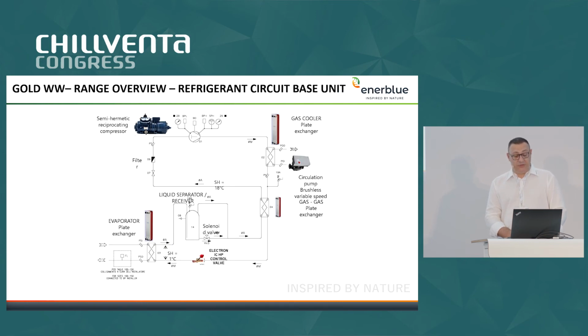For this unit, we have more or less the same schematic we saw for the air-to-water, but at the end, it is probably a little bit simpler compared to the air-to-water because we have, instead of the coil and the fan, another heat exchanger on the source side. So, as I said before, we keep it simple in order to have a reliable product and to always be able to find spare parts. So something very, very simple.